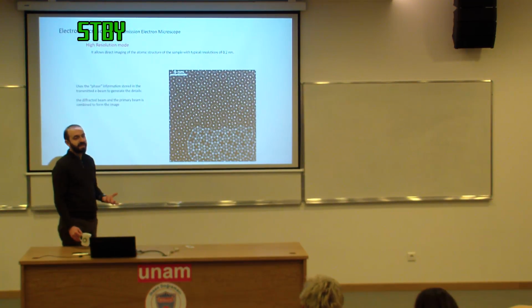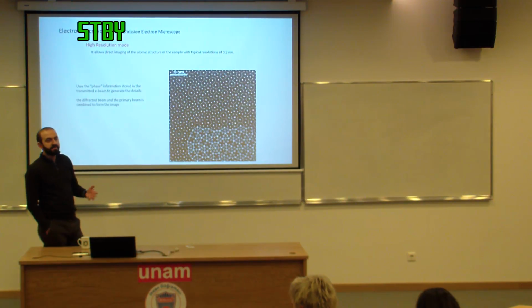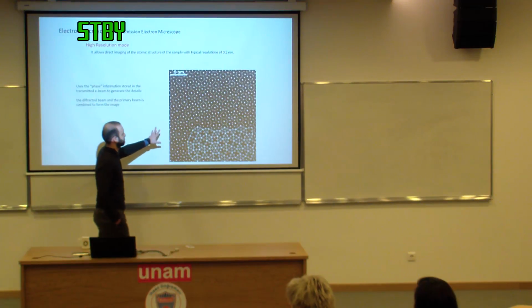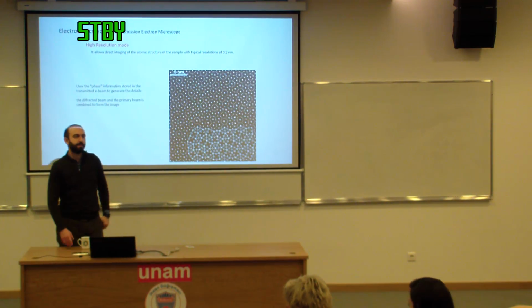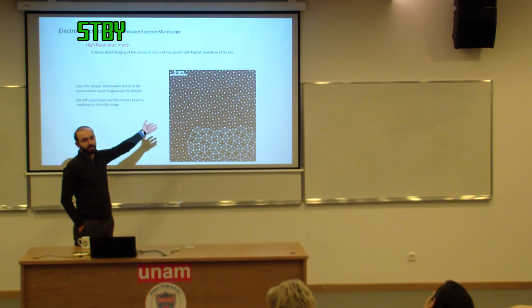Well, all the modes have limitations. If you have a very thick sample, let's say you want to take a diffraction pattern from a sample which is coated with a polymer, forget about it, it's not going to work. Polymers are nasty stuff. If you have a 500 nanometers thick polymer, it's not going to work. If you have a few molecules of polymer, maybe. But typically, if you're really after this high resolution, you need a perfect sample, very thin, very clean. Otherwise, what you get is just a cloud of blurriness. You don't get this high resolution. And if you go to SEM, it's a totally different story. You cannot even imagine going down to these resolutions.